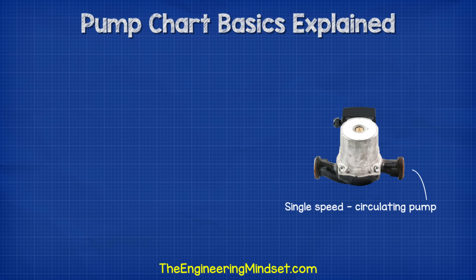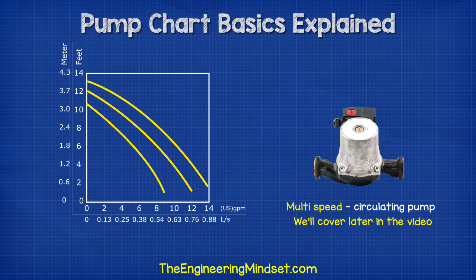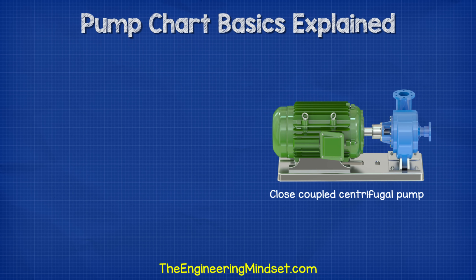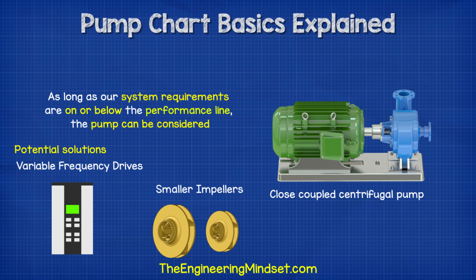When selecting a circulating pump, the pump will only perform as per the line. So for this model, if we wanted 8 gallons per minute, then we would have 6 foot of head. You can also get multi-speed circulating pumps which we'll look at later on in this video. When selecting a larger centrifugal pump, as long as our system requirements are on or below the performance line, then the pump can be considered. We can potentially use a smaller impeller or variable frequency drive to better suit our requirements, and we're going to look at that a little later in this video.